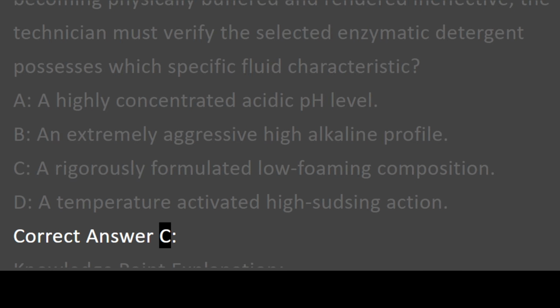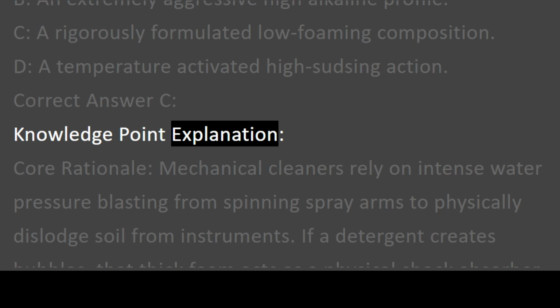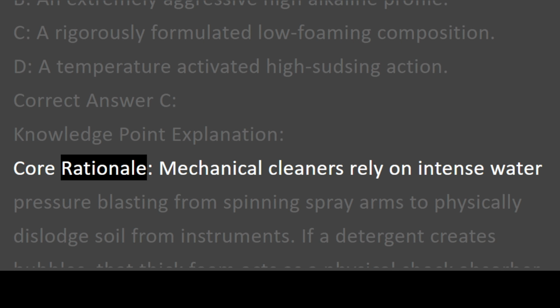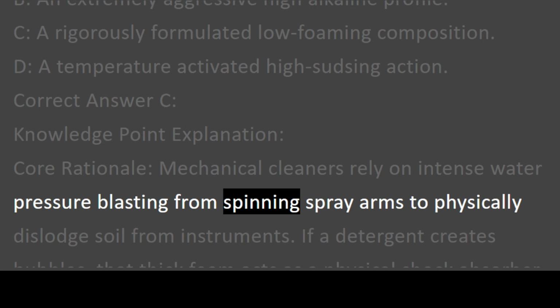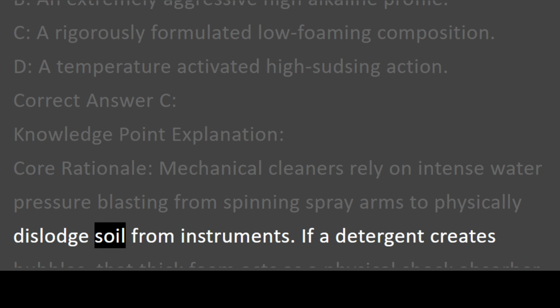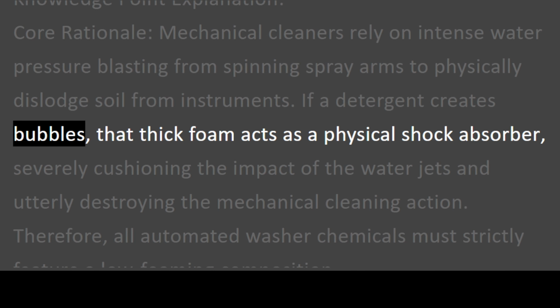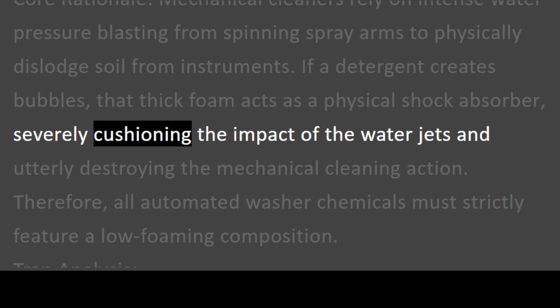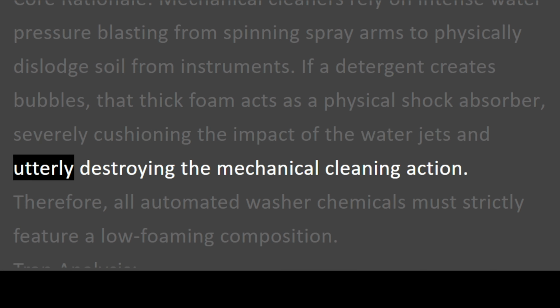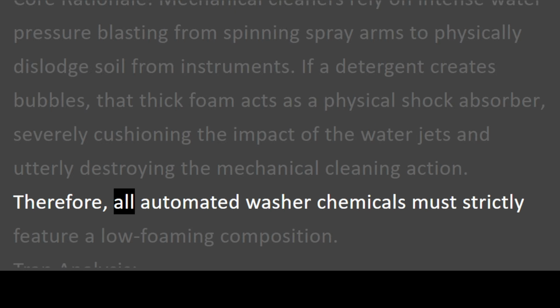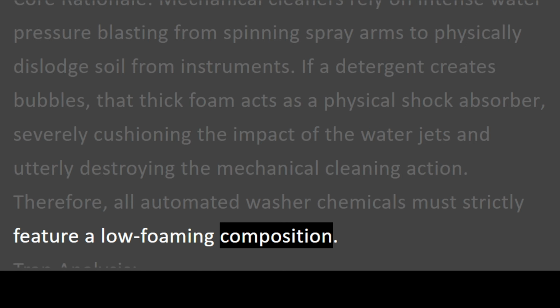Correct answer C. Knowledge point explanation. Core rationale. Mechanical cleaners rely on intense water pressure blasting from spinning spray arms to physically dislodge soil from instruments. If a detergent creates bubbles, that thick foam acts as a physical shock absorber, severely cushioning the impact of the water jets and utterly destroying the mechanical cleaning action. Therefore, all automated washer chemicals must strictly feature a low foaming composition.